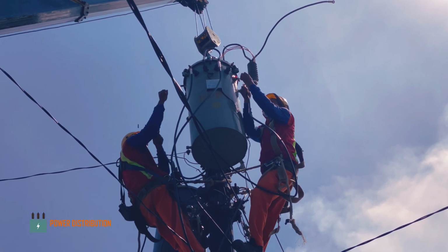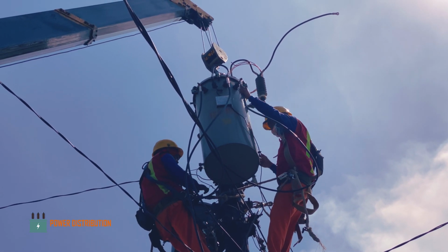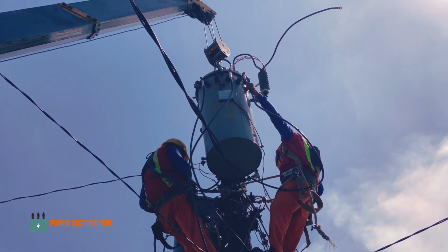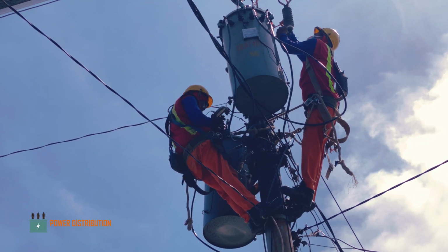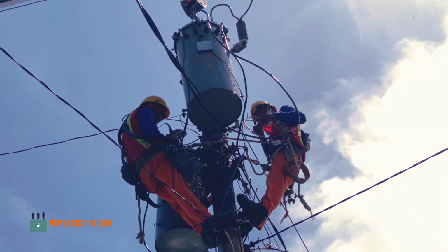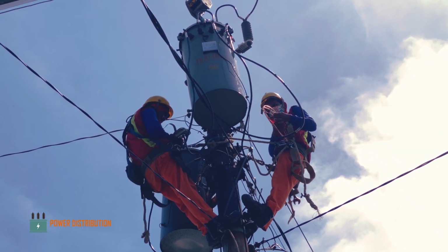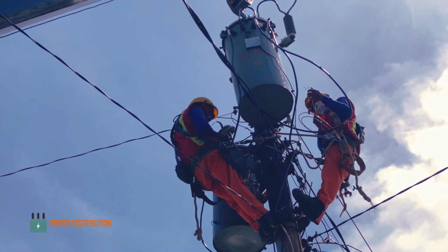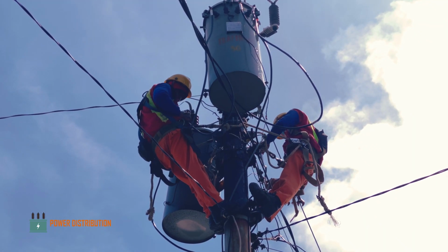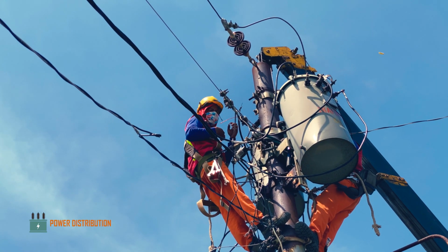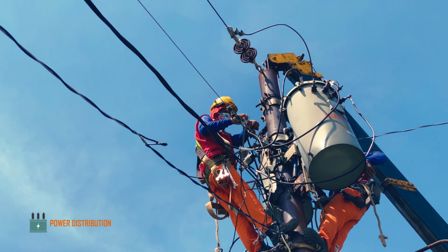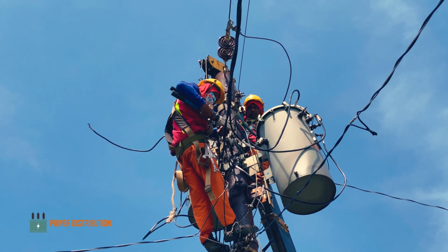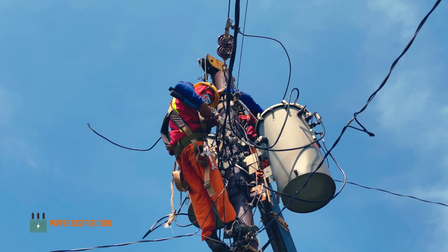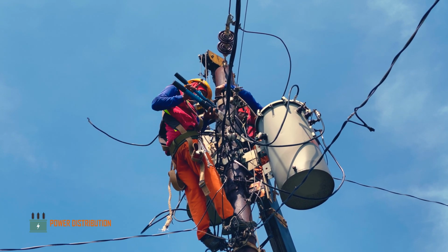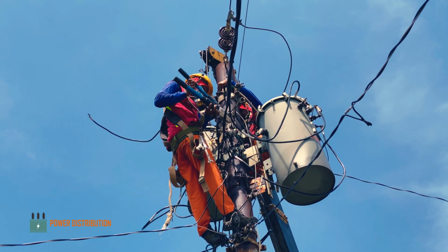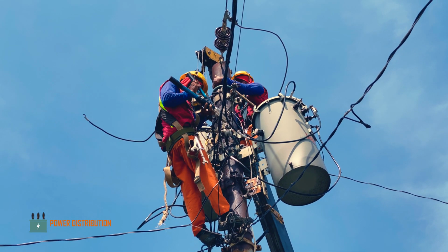Back to the installation process, now the transformer is firmly in place and the crew are preparing all the connections necessary to make this transformer work properly. The right crew prepares the bare copper conductor to hook the grounding pad from the new transformer body into the existing grounding pad on the pole. Then he connects the neutral wire from the primary and the secondary bushing to the common neutral on the pole. Then he secures the connection using a compression connector and hydraulic press.